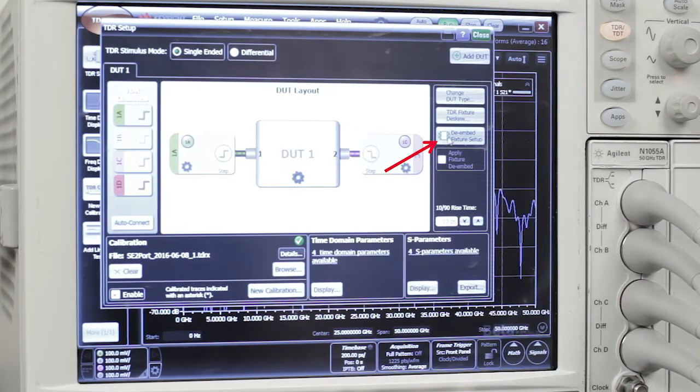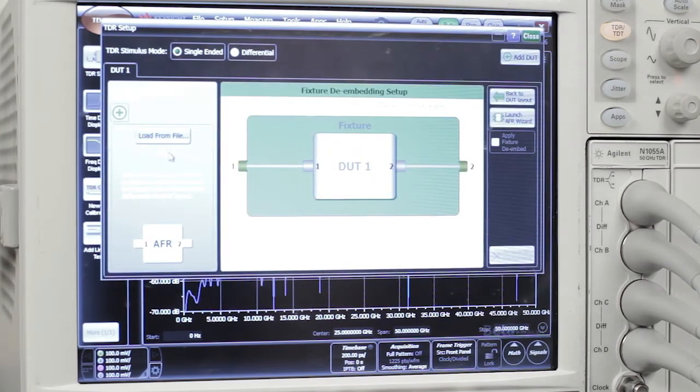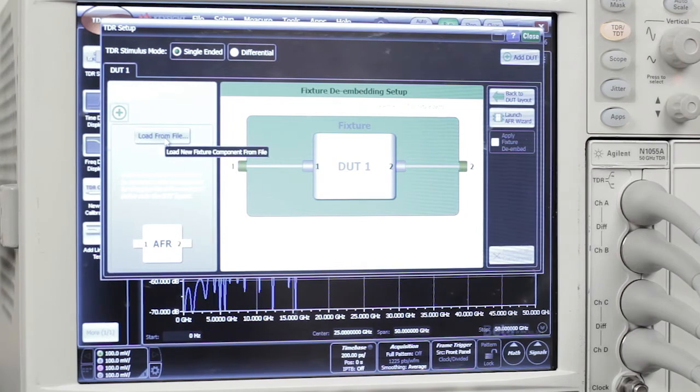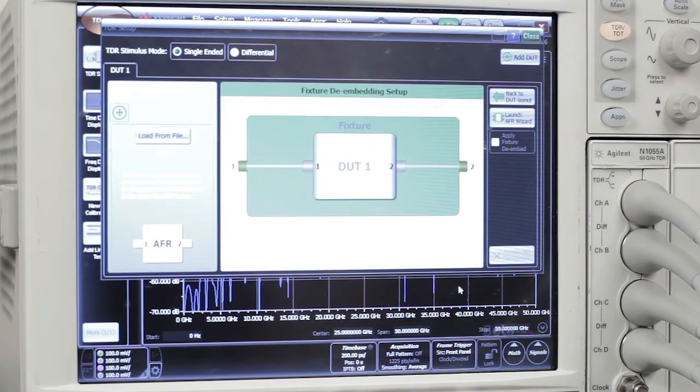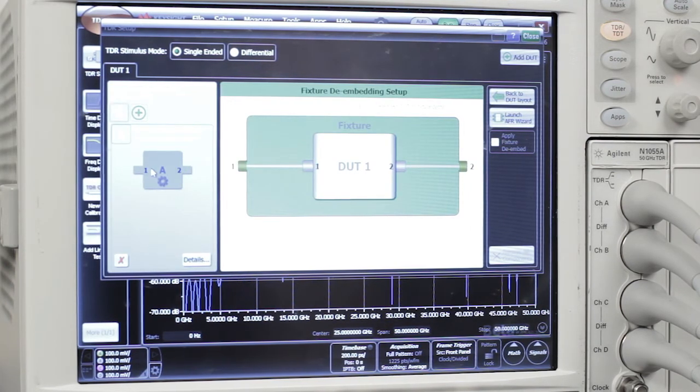We go back to the setup and into our de-embed setup. We just need to now find the S-parameter file for our fixtures. So we're going to load that S-parameter file, which is on the desktop. We're going to select that. And now I can put this for each port.